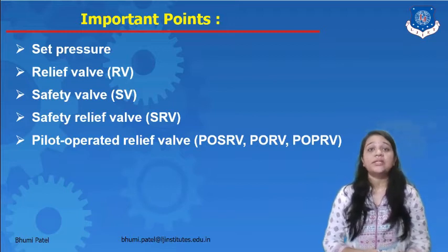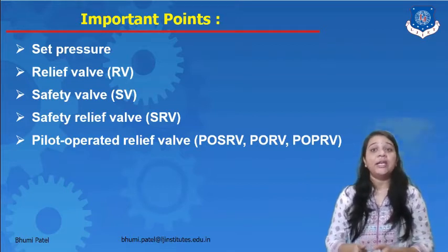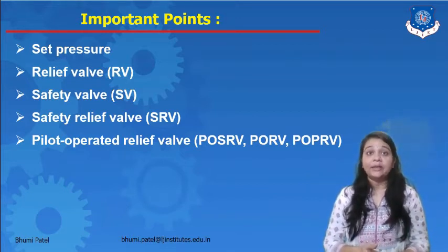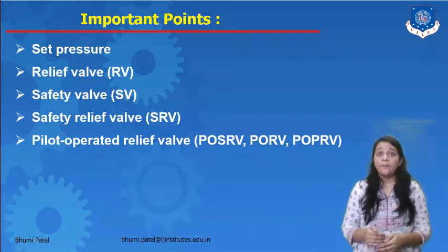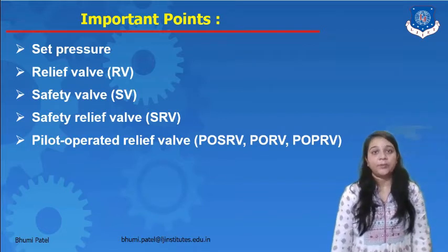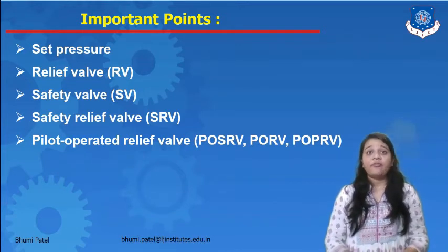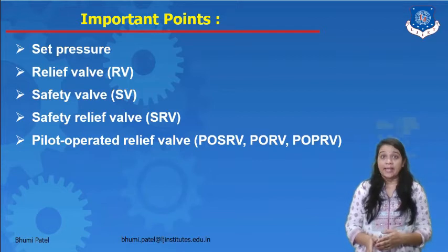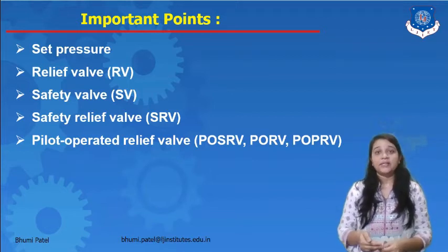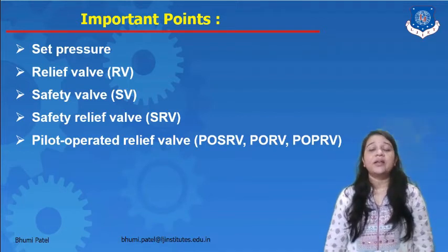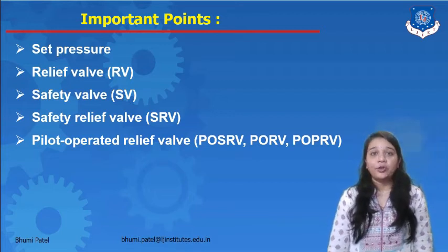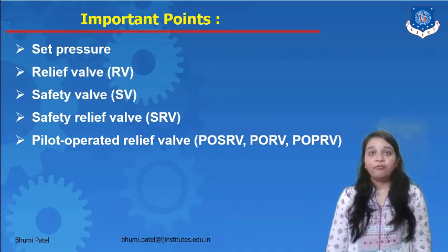Most safety valves are full lift or snap acting, in that they are completely open in position. Now the fourth one is the safety relief valve, a relief valve that can be used for gas or liquid service. However, the set pressure will usually only be accurate for one type of fluid at a time.